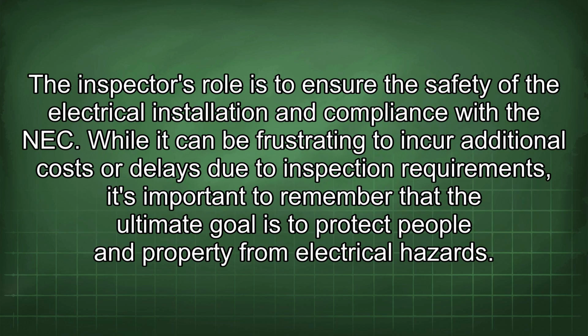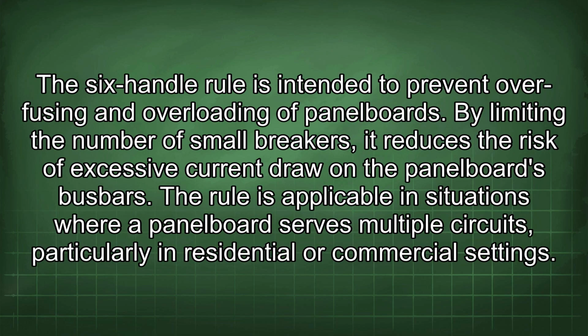The inspector's role is to ensure the safety of the electrical installation in compliance with the NEC. While it can be frustrating to incur additional costs or delays due to inspection requirements, it's important to remember that the ultimate goal is to protect people and property from electrical hazards. The 6-handle rule is intended to prevent overfusing and overloading of panel boards. By limiting the number of small breakers, it reduces the risk of excessive current draw on the panel board's busbars.